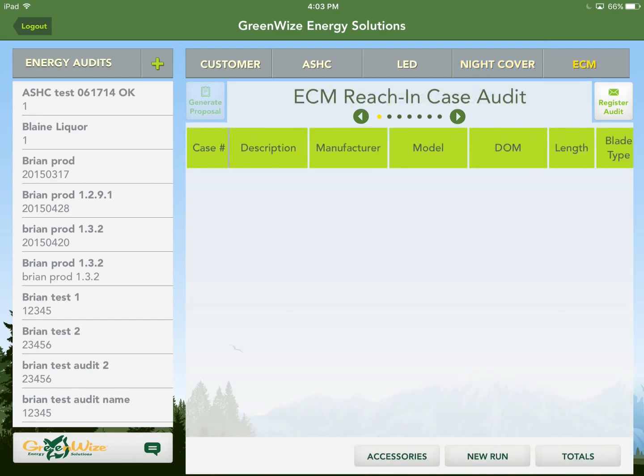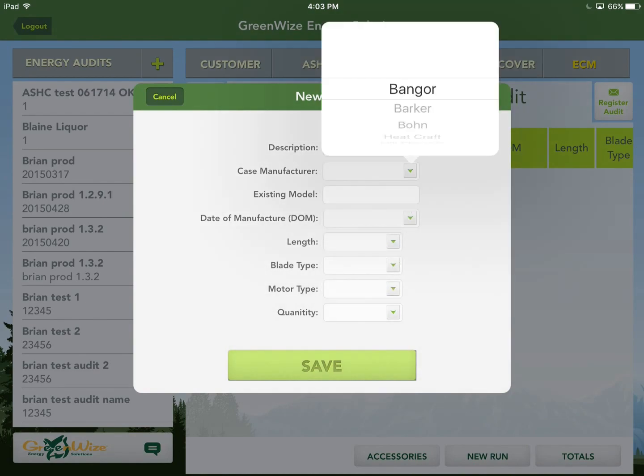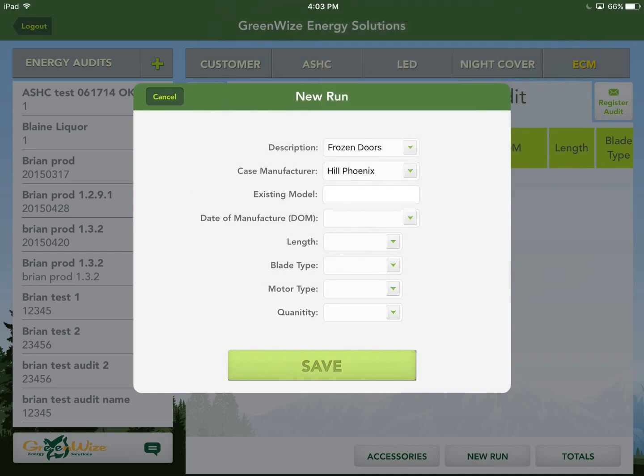Now let's do the ECM reach-in case audit. This is for frozen doors and also areas like produce where there are reach-in motors underneath the drip pan. We'll do a run for frozen doors — 10 doors, about 2.5 feet each, so roughly 25 feet. For blade type: if you encounter plastic blades, it's recommended to replace them with metal ones since plastic can become brittle and even break during motor replacement. We'll choose metal. For motor type, we'll choose shaded pole — the more common of the older style motors. Quantity: one motor per door, so 10.